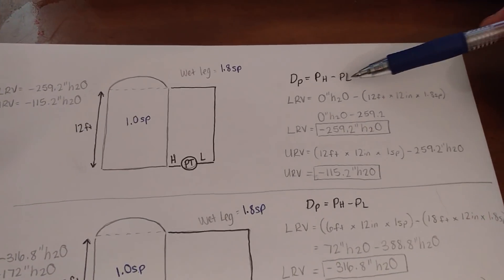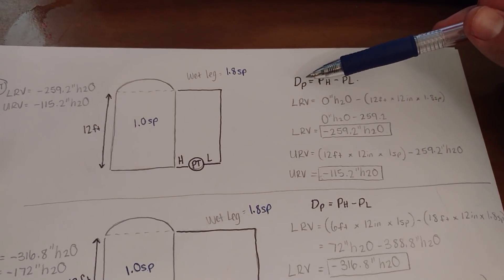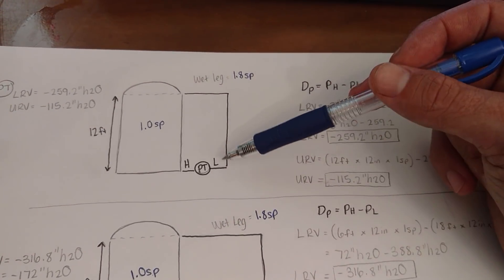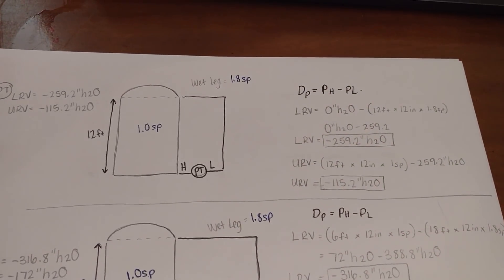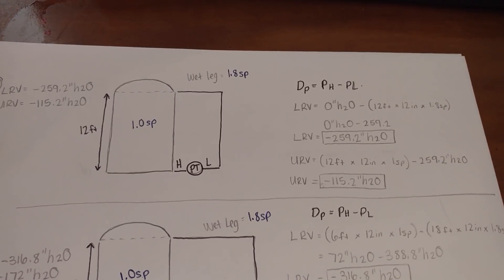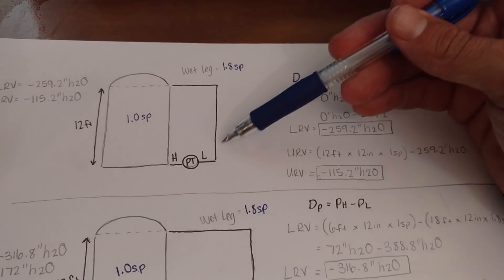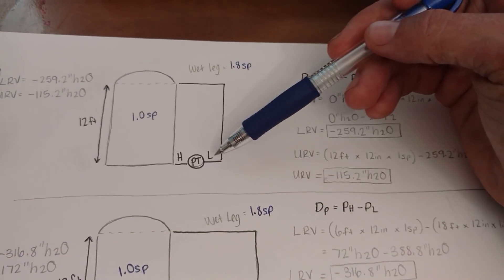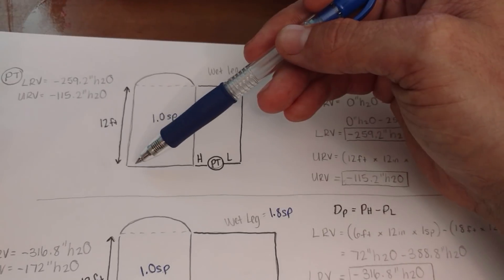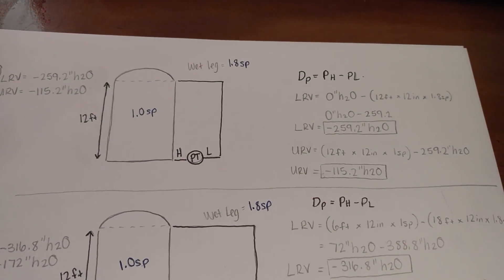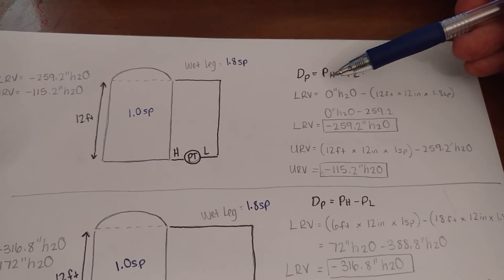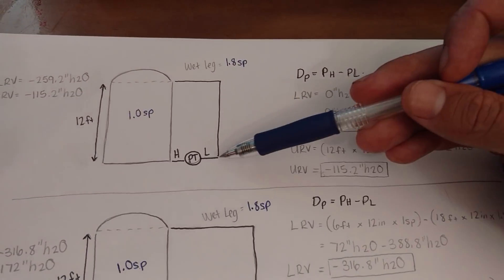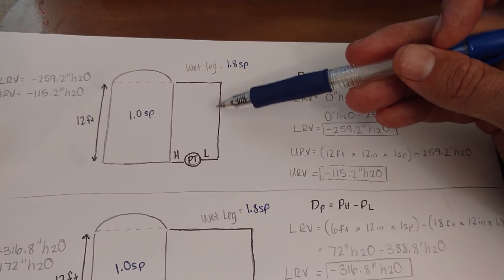We're going to use this formula: differential pressure equals pressure high minus pressure low. For the lower range value in this situation, we have 0 inches H₂O for our pressure high side — 0 inches because our pressure transmitter is actually even with the base of this tank, which would be at 0 feet of water. So we're going to have 0 inches H₂O for our pressure high, minus our pressure low side, which is going to be this hydrostatic pressure here.